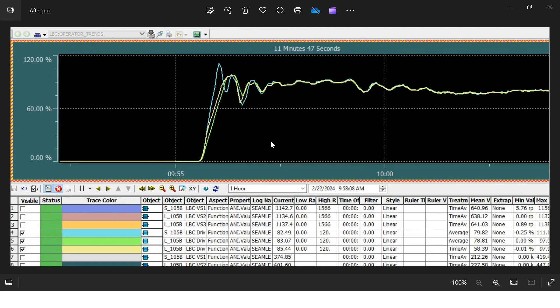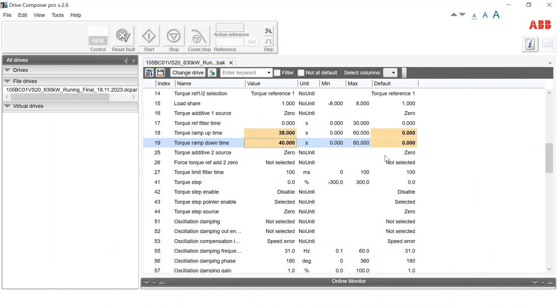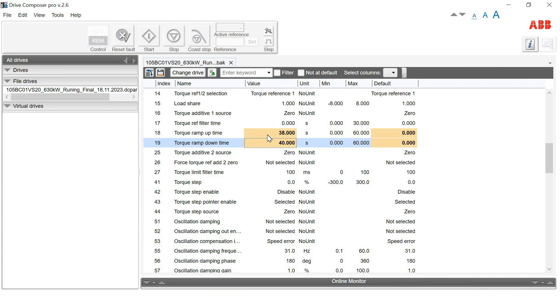The speed difference was also negligible. We did not change the value further, because the starting current difference was only about 5 to 10 amperes, which was negligible. So we kept the torque ramp time at 38 seconds and now it is running perfectly. So if you face any issue when you configure a Master-Follower drive, you have to check that parameter — the torque ramp time in the reference chain.